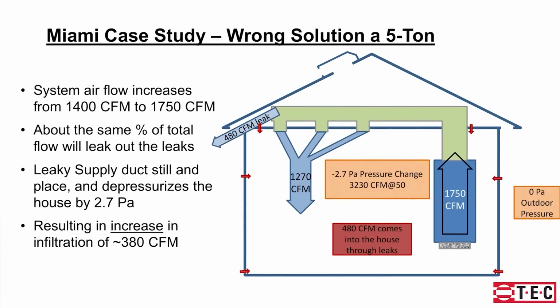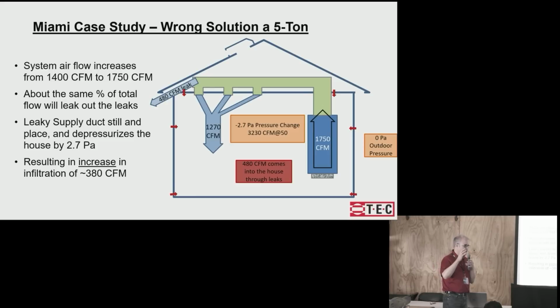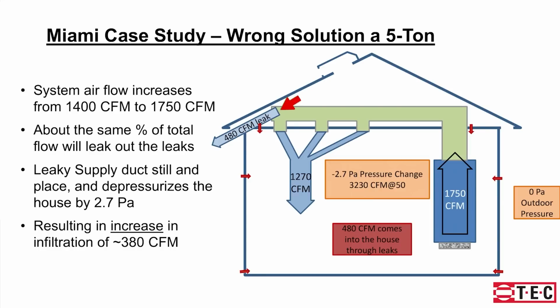5-ton system, now we're up to 1750. We're going to have the same percentage leaking out and coming in. That's how the flow is going to work in the duct: if 25% was leaking, you're going to have 25% leaking with a bigger system too, if you can get there even. So now we've got 480 CFM leaking to outside and 1270 coming back in. We had a -2 Pascal pressure change before. That's going to go up to something like -2.7. So we're getting closer to a 3 Pascal depressurization now with the bigger system in.